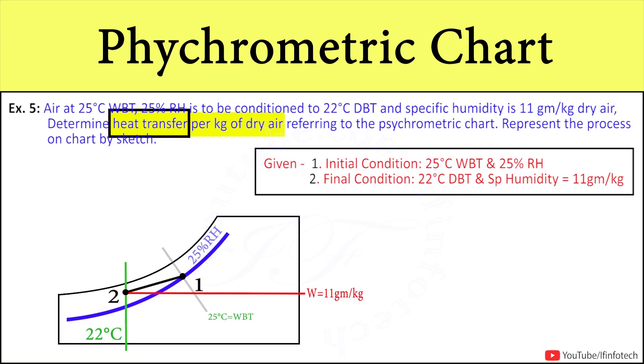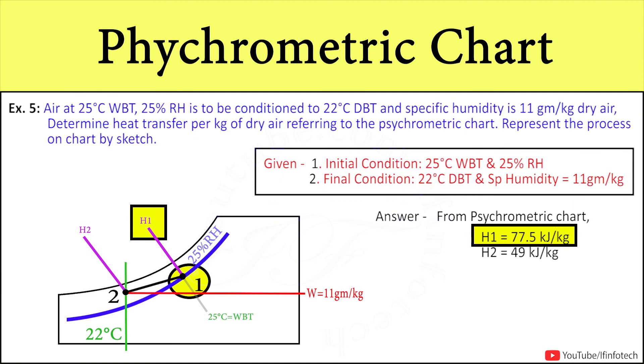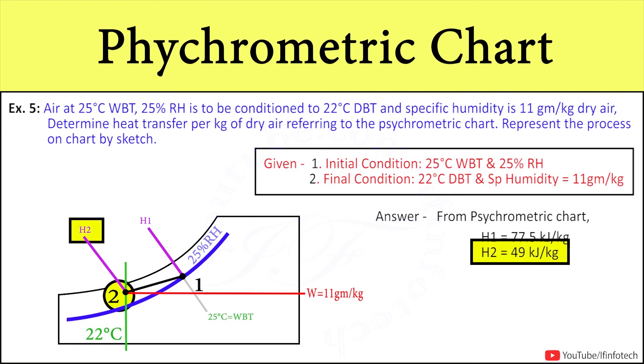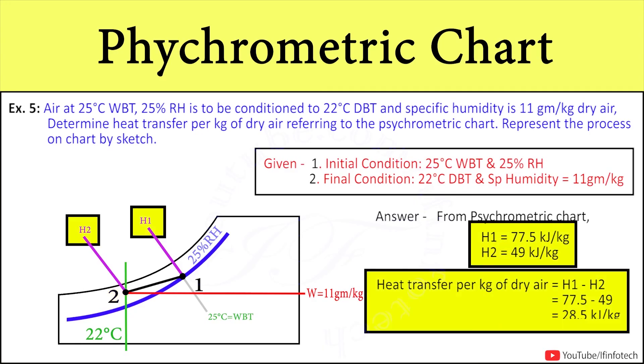In order to calculate change in heat, we need to find out enthalpies at point 1 and point 2. Enthalpy at initial condition, i.e. at point 1, is 77.5 kJ per kg, and at final condition, i.e. at point 2, the enthalpy is 49 kJ per kg. Putting values of H1 and H2, we get the heat transfer per kg of dry air as 28.5 kJ per kg of dry air.